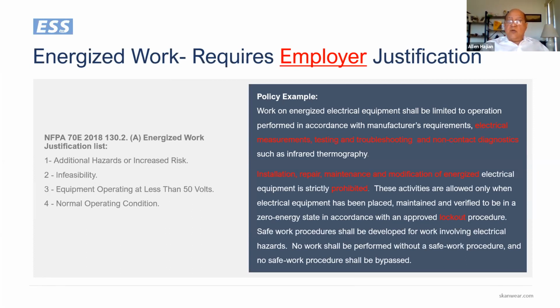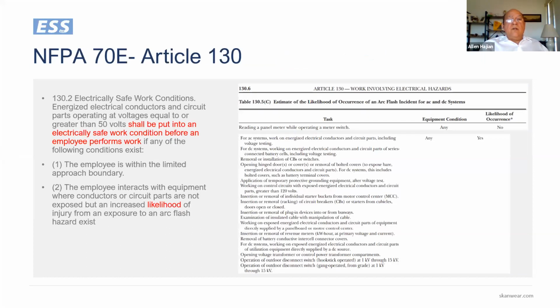So, for example, in the same policy examples, electrical measurement, testing, and troubleshooting is part of justification for energized work under infeasibility. Installation, repair, maintenance, and modification of energized electrical equipment is prohibited because it can be done, or has to be done, in a de-energized state. So make sure you understand the justifications and why some work is allowed in an energized state and some work is not. Article 130 starts with: shall be put into an electrically safe work condition before an employee performs work. So that's the overriding factor.